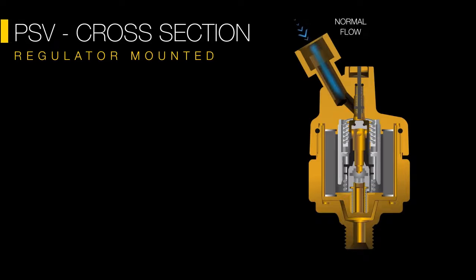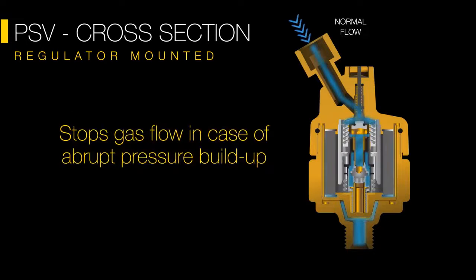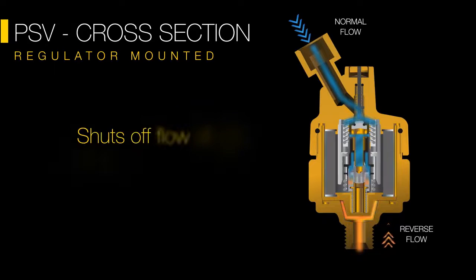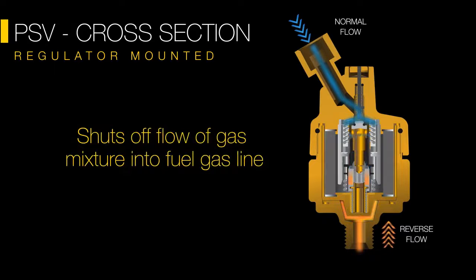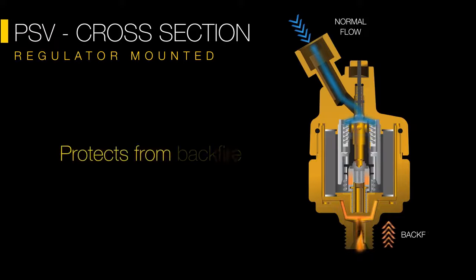The pressure sensitive cutoff valve allows free flow of gases as long as there is a stable pressure. The valve gets activated and cuts off flow in case of sudden pressure buildup. It shuts off and arrests gas flow, limiting the flame from spreading.